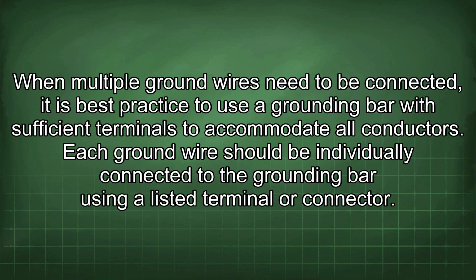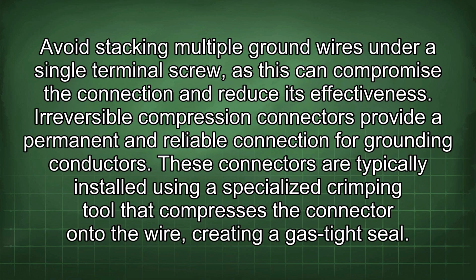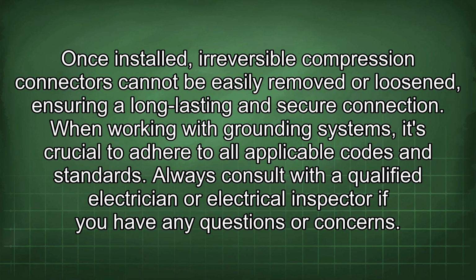When multiple ground wires need to be connected, it is best practice to use a grounding bar with sufficient terminals to accommodate all conductors. Each ground wire should be individually connected to the grounding bar using a listed terminal or connector. Avoid stacking multiple ground wires under a single terminal screw, as this can compromise the connection and reduce its effectiveness. Irreversible compression connectors provide a permanent and reliable connection for grounding conductors. These connectors are typically installed using a specialized crimping tool that compresses the connector onto the wire, creating a gas-tight seal. Once installed, irreversible compression connectors cannot be easily removed or loosened, ensuring a long-lasting and secure connection.